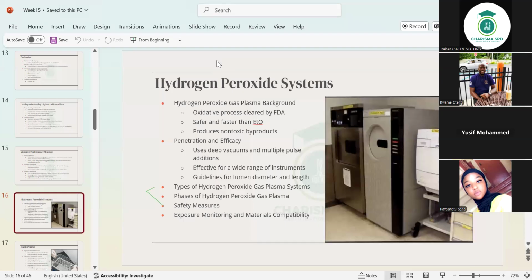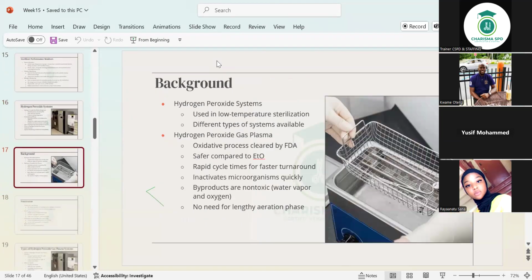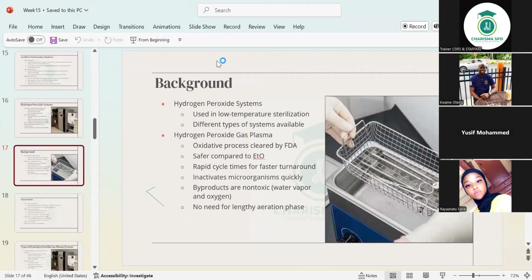Okay, the injection and plasma phases are repeated a second time. That is after the diffusion, after the exposure. Right, then there's a vent. So you have 5 stages, which are the vacuum, the injection, the diffusion, the plasma, and then the vent. This one requires no aeration because the byproducts are water vapor and oxygen. So you don't need aeration in this. All right. Any questions? I think I've taken care of all this now.